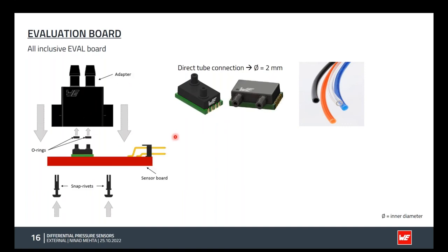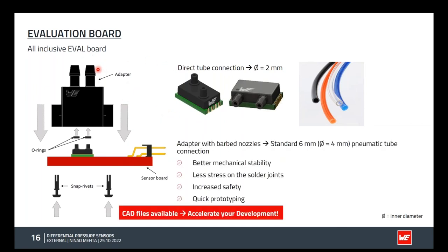But with our evaluation board, you also get an adapter and O-rings for the sealing, which you can use for your prototyping, where you can use the standard 6 millimeter pipes to connect to the sensor. And this is very important in terms of mechanical stability, because the electrical joints of the sensor, or the soldering joints, are not made to withstand the mechanical stress that comes with the pipes connected. So when we use this adapter, there is less stress on the sensor, and also in terms of hazardous gases, when there is a danger of leakage, this provides additional safety.